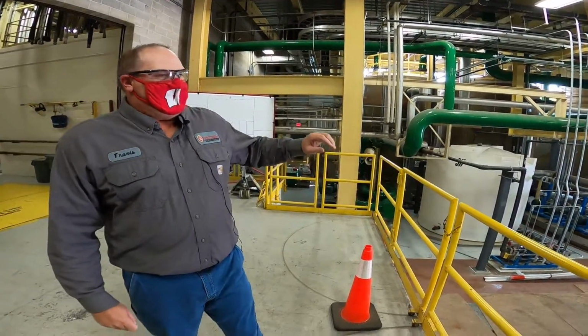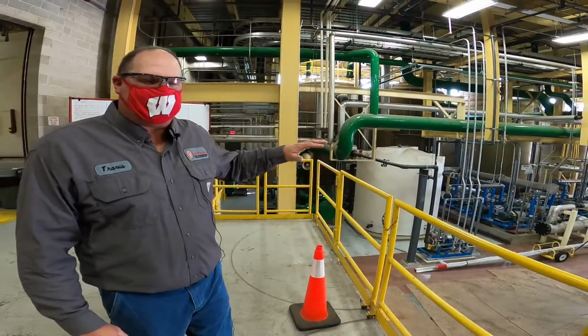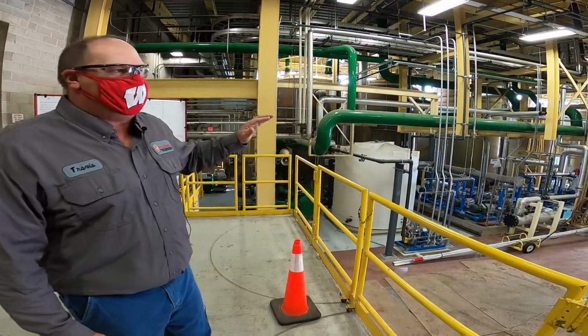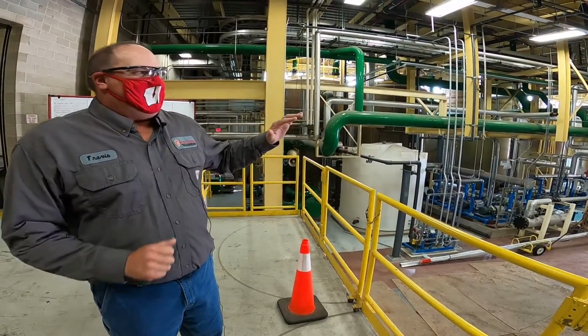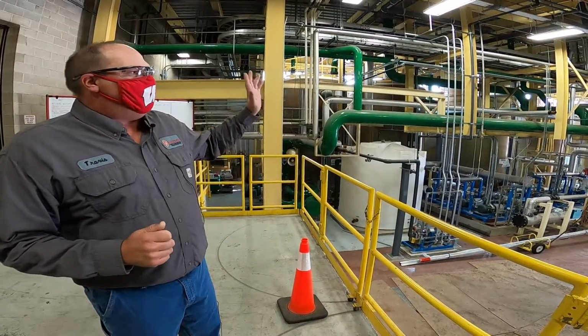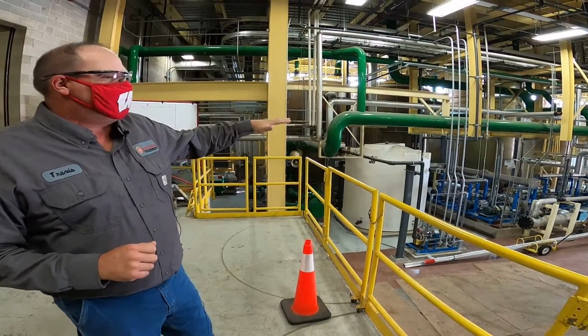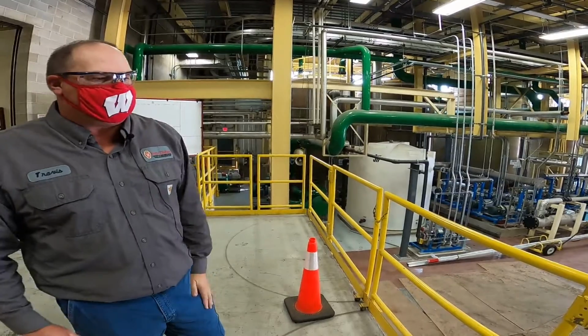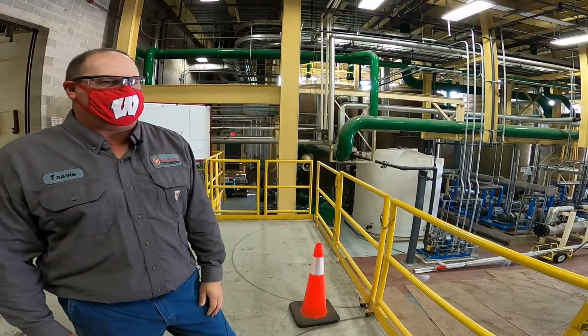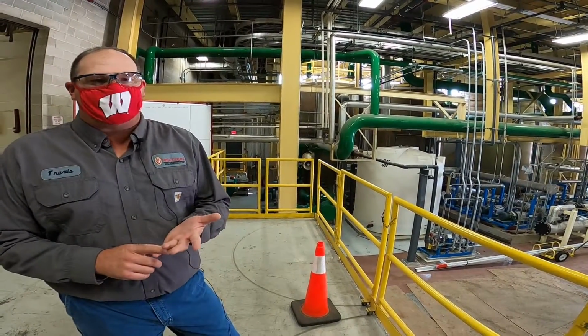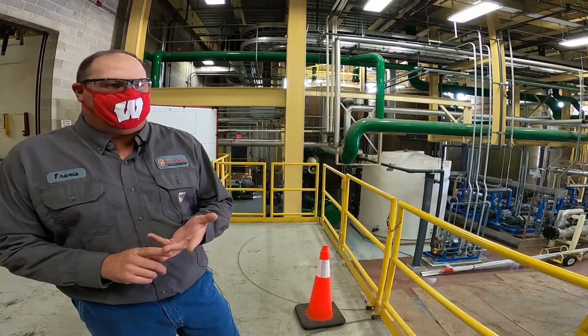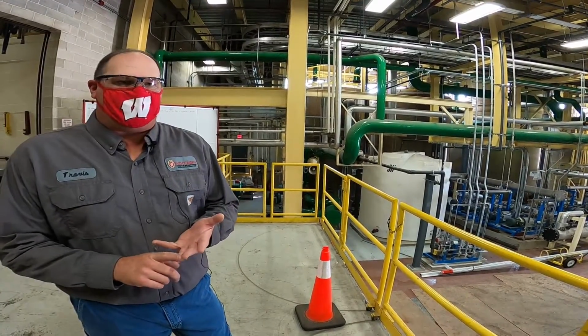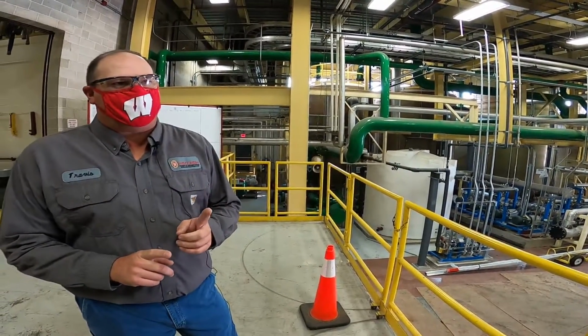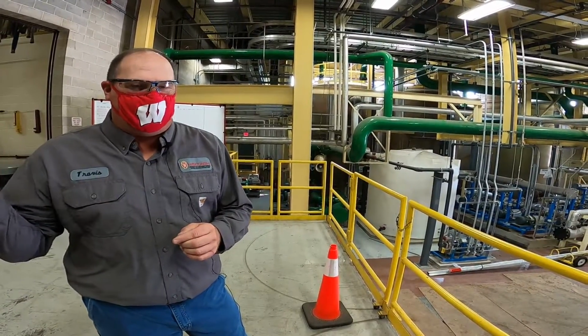So it's a very complex water treatment system to filter out all the bio and iron, calcium, magnesium out of that system. We have 2 floors. This is the first floor, second floor being upstairs where our reverse osmosis units are. And we can produce up to 450 gallons a minute of RO water for our system, which is enough to operate 1 of the 4 boilers at full capacity.